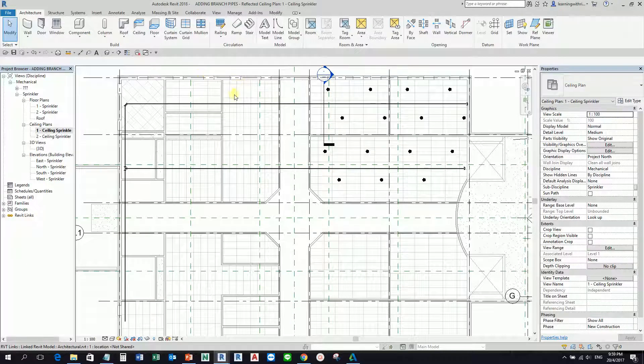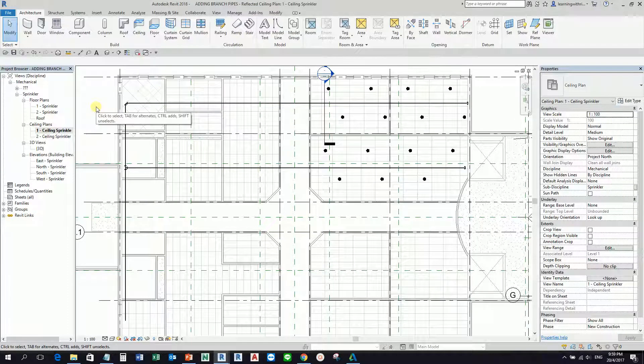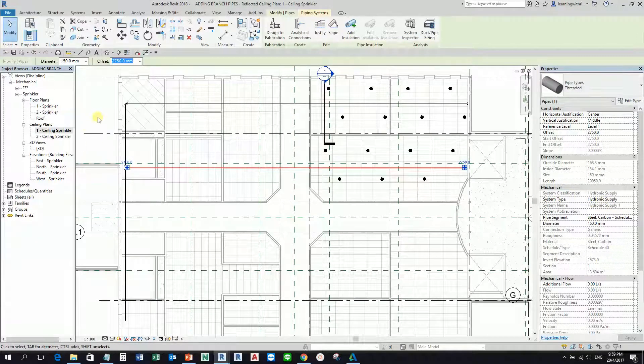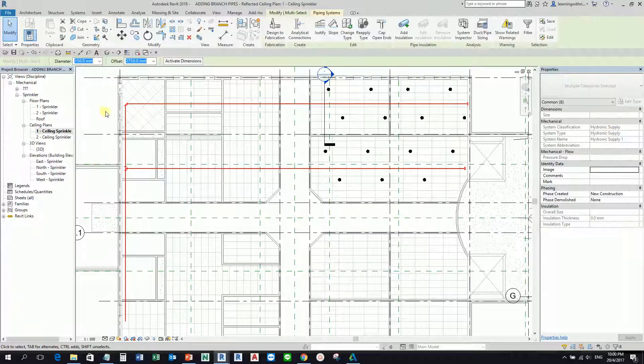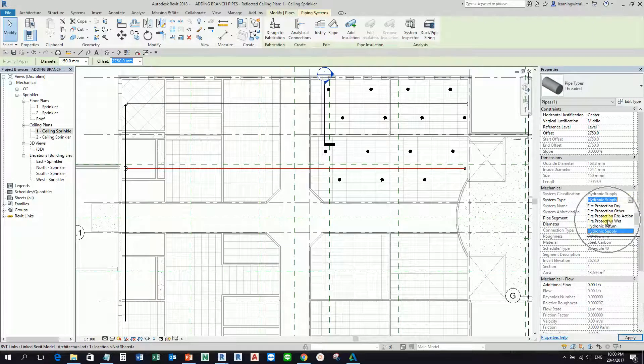Before I connect the sprinklers to my pipe, let's say you created your main pipes with the wrong system type — for example, if I select the pipe here, you'll notice the system type is 'Hydronic Supply.' Do not select all the pipes at once because you won't be able to change the system type that way. Instead, select just one pipe, click the drop-down arrow on the system type, and select 'Fire Protection Wet,' since my sprinkler here is wet.